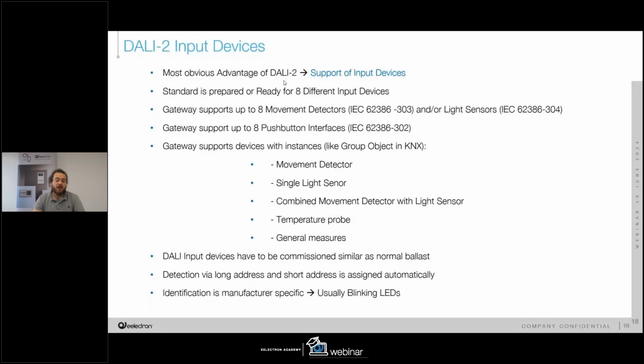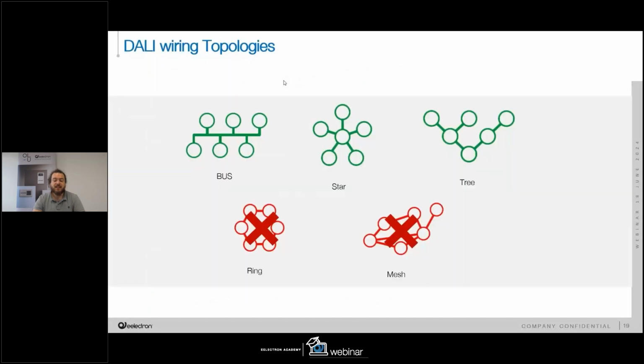Regarding the topology of the DALI, it's very similar to KNX, so we can have a bus connection, star connection, or tree connection. We can also mix these three kinds of topology. Remember that you don't have to close any ring in your DALI bus, and neither wire any mesh network between devices. So it's like the KNX protocol.